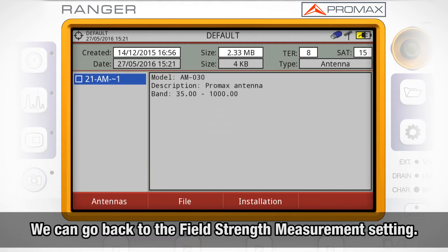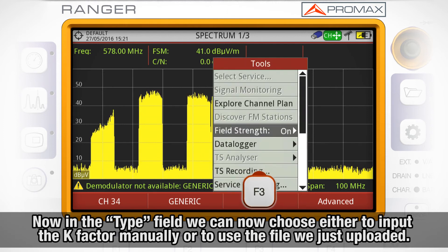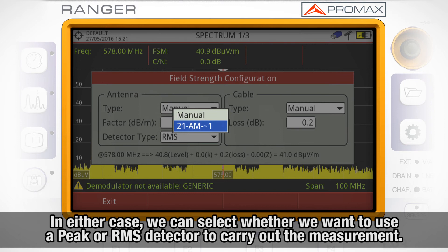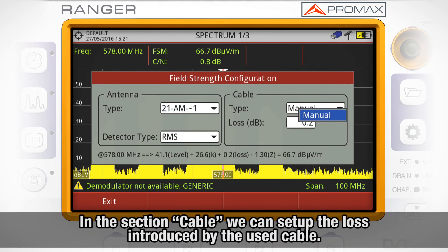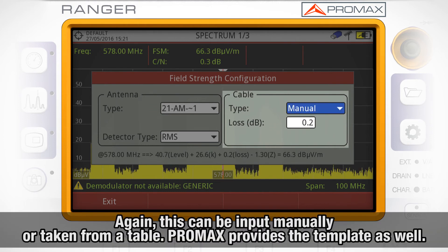Now we can go back to the field strength measurement setting. There, in the Type field, we can now choose either to input the k-factor manually for the currently tuned frequency, or to use the file we just uploaded for the AM030 antenna. In either case, we can select whether we want to use a Peak or RMS detector to carry out the measurement. In the Cable section, we can set up the losses introduced by the cable used to connect the antenna to the meter. Again, this can be input manually or taken from a table.